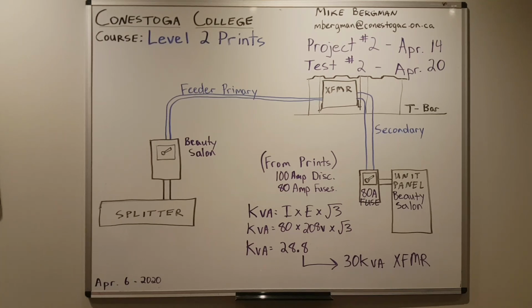So your kVA is going to equal the current ampacity, or the possible ampacity we could supply, the current times the line voltage, which is 208 because it's the secondary of the transformer, times square root 3. So I took the 80, which is 80% of 100. So 80 times our line voltage on the secondary, which is 208 volts, which hasn't changed from our original prints, times the square root of 3 because it's three-phase. I get a kVA equals 28.8.